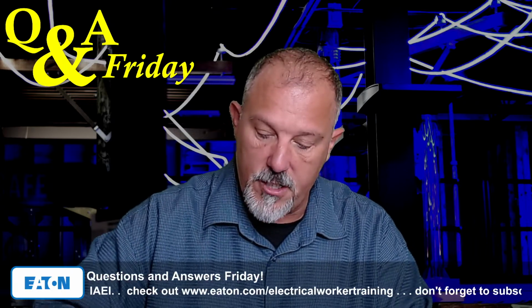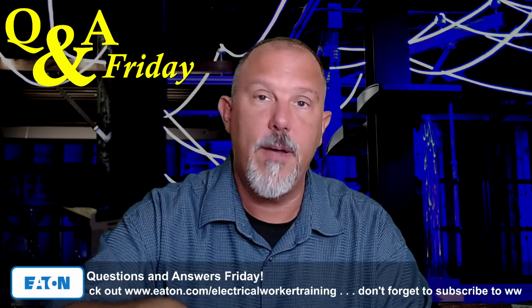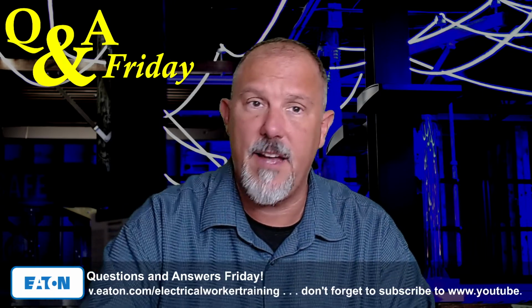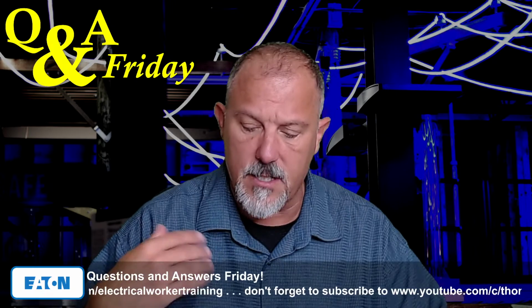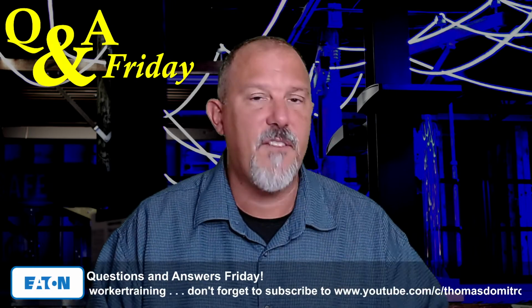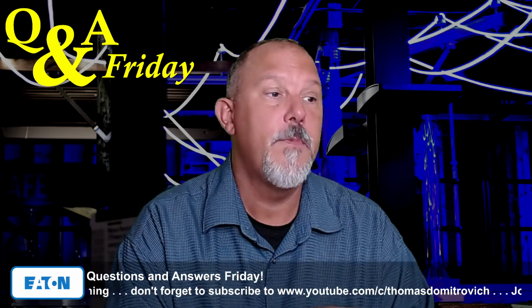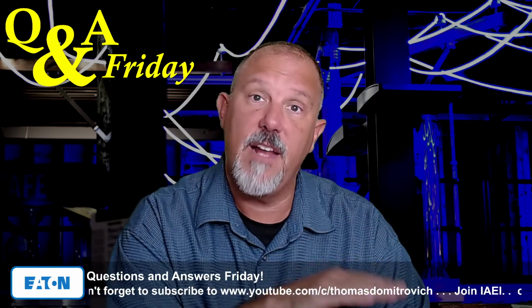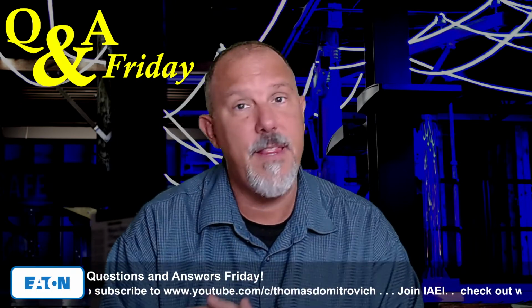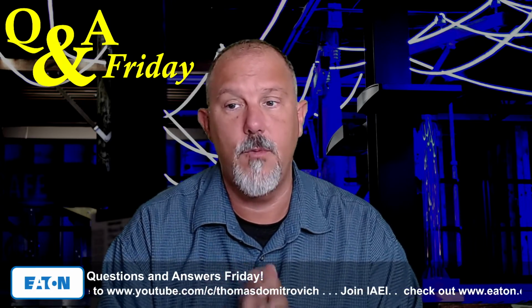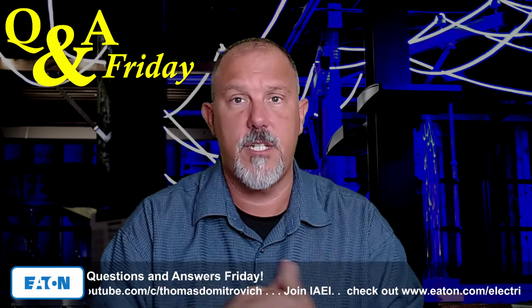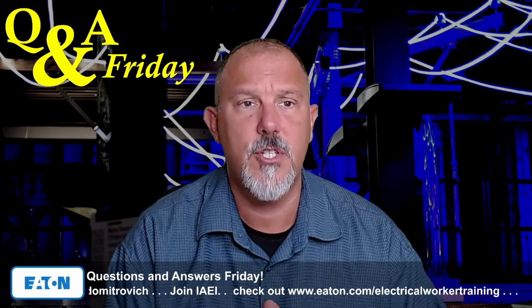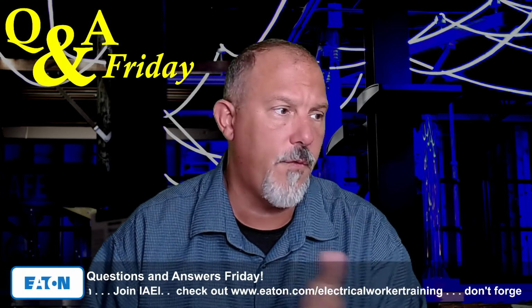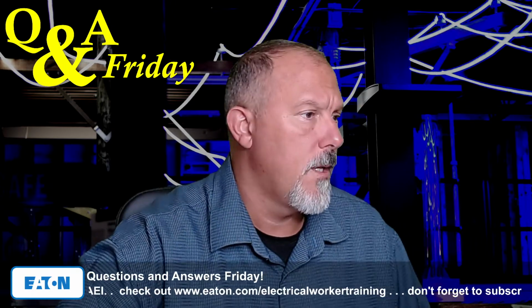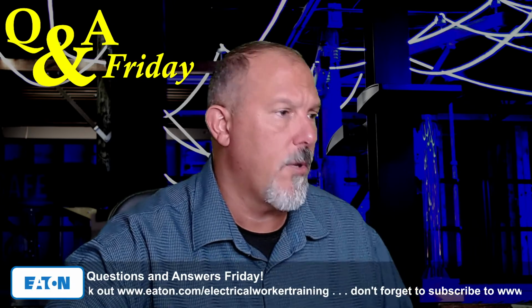There is permission for that. You have to think about how you protect it. You may have to size your overcurrent protective devices a little differently. But yes, you can backfeed through a transformer. I would not use my information in that video for a transformer that's fed in a backfed situation. I would suggest that you should think the inrush currents are going to be a little different. So always talk to the manufacturer. So hopefully, Earl, that helps you. Thanks for the question. I really appreciate that.